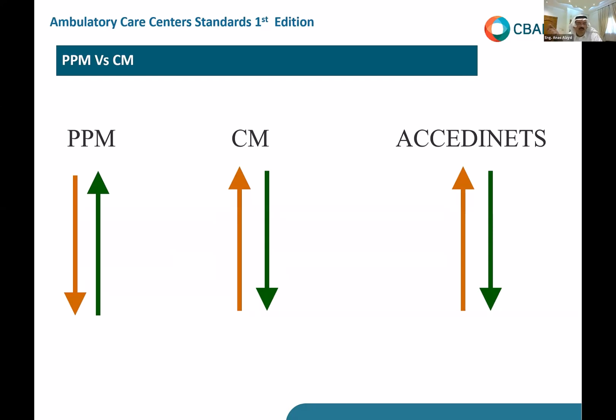So please, when the standard talks about PPM, we want to see first that you're doing a PPM program, preventive maintenance, for all your equipment: air conditioning, generators if you have, elevators, power outlets, everything, autoclaves, the medical equipment, analyzers, the lab equipment, all of it. We need to see a PPM on it. And we need to measure how many PPMs you do versus how many corrective maintenance. Corrective maintenance means something broke, somebody calls, and you go and repair it. Preventive maintenance, you do maintenance before it breaks down. So this is the difference between them, and accidents are correlated with corrective maintenance. The higher the corrective maintenance you do, the higher the accidents, and vice versa. The lower the corrective maintenance, the lower the accidents. That's a very, very important rule.